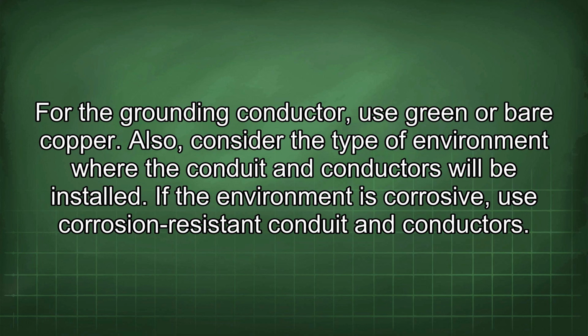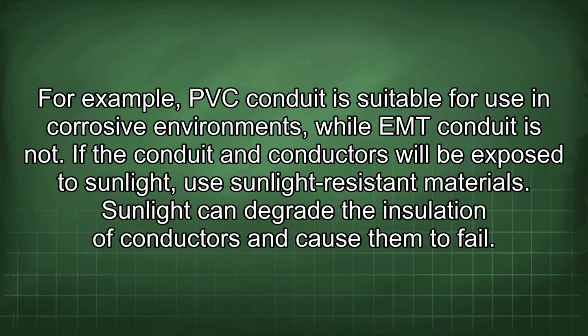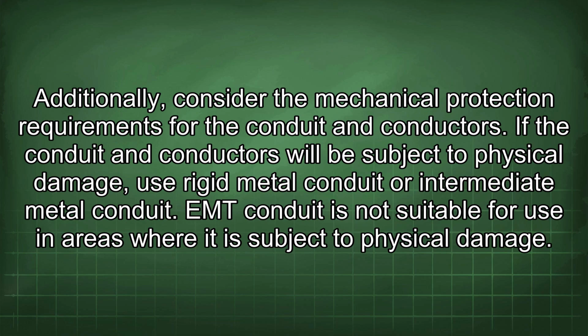Also, consider the type of environment where the conduit and conductors will be installed. If the environment is corrosive, use corrosion-resistant conduit and conductors. For example, PVC conduit is suitable for use in corrosive environments, while EMT conduit is not. If the conduit and conductors will be exposed to sunlight, use sunlight-resistant materials. Sunlight can degrade the insulation of conductors and cause them to fail. Additionally, consider the mechanical protection requirements for the conduit and conductors.